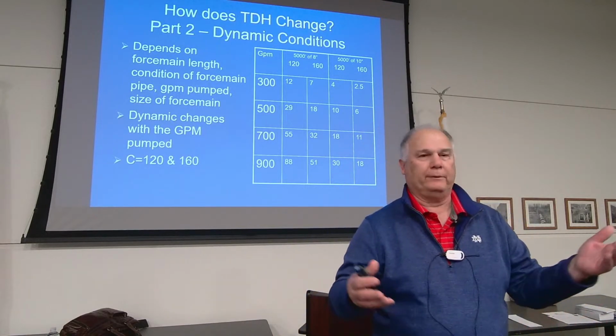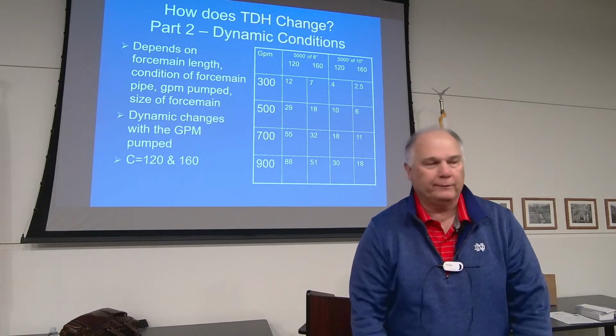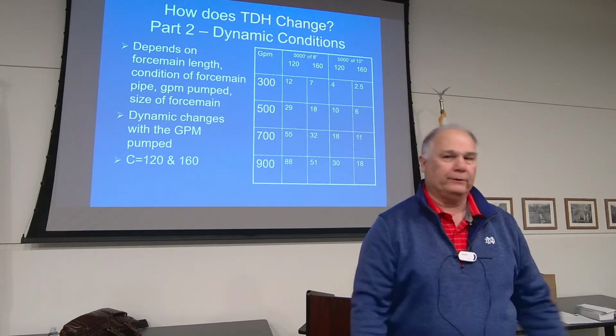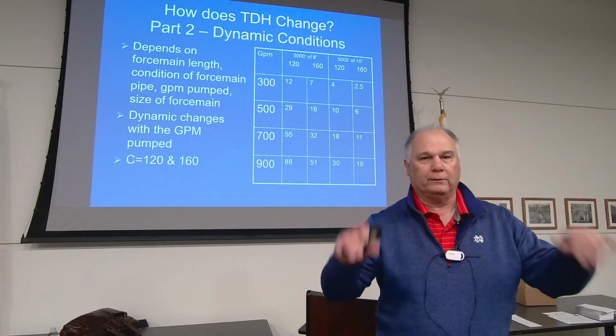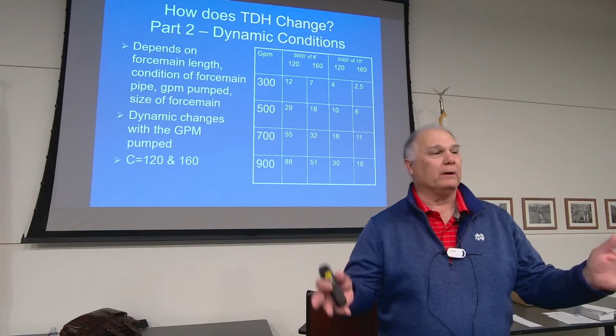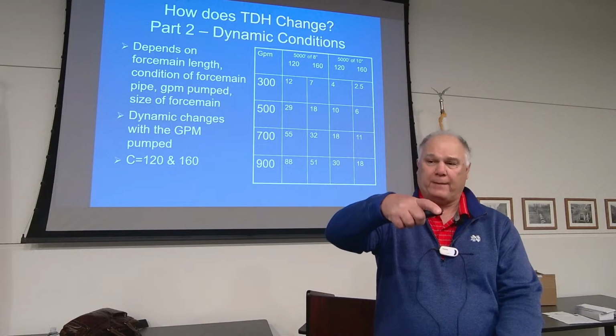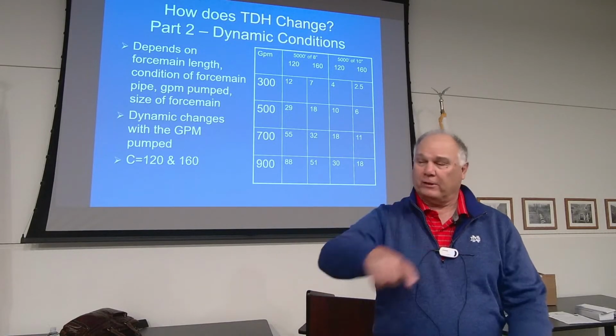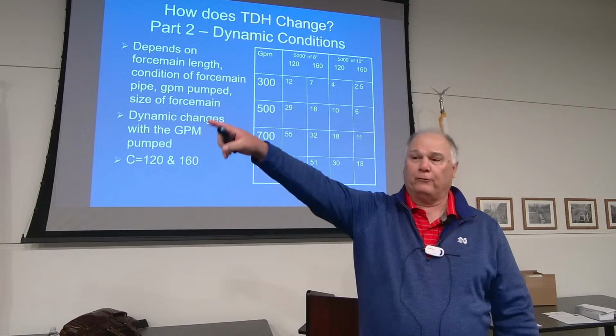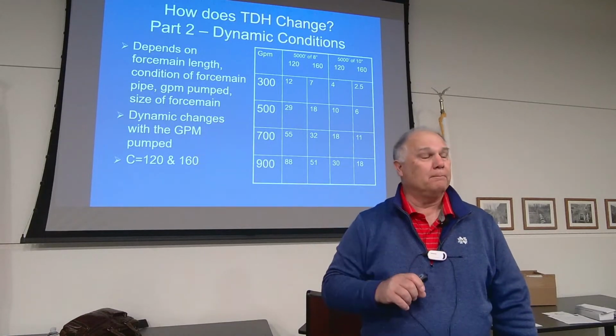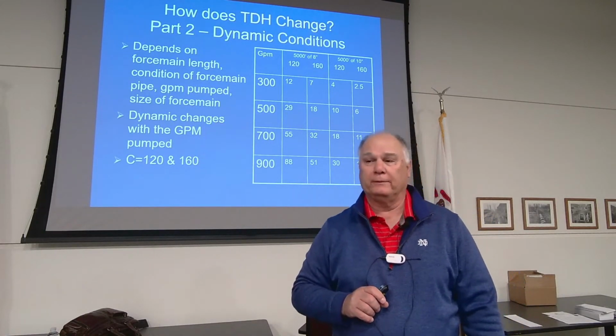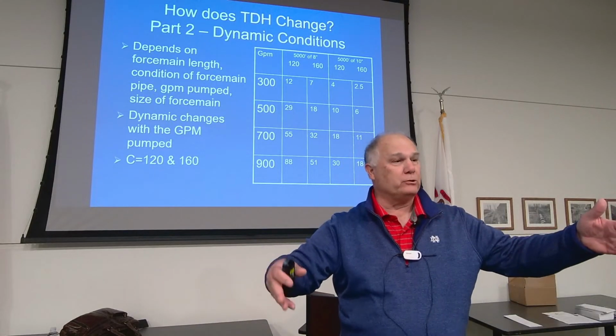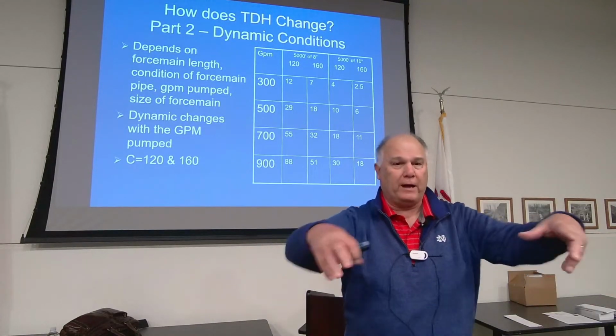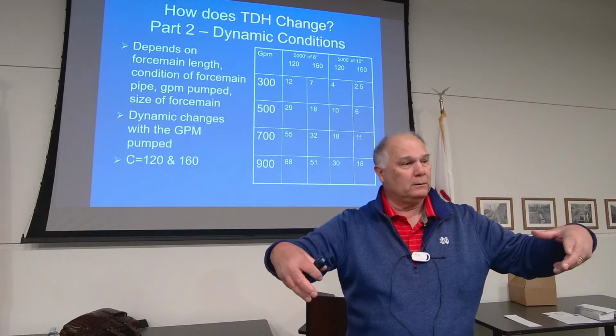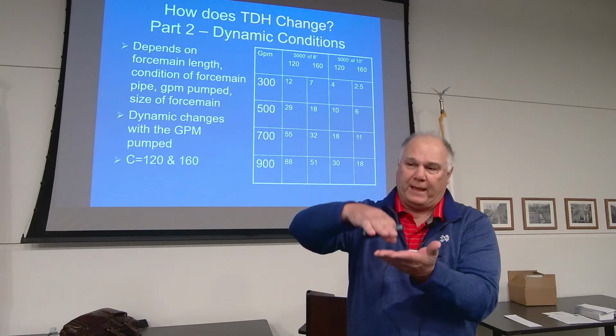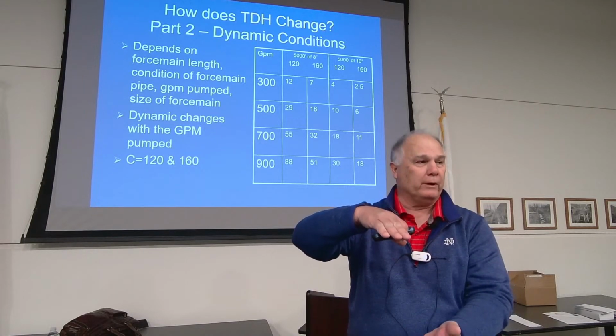So they say, oh, we're only pumping 10 gallons a minute. It's supposed to be doing 1,000 gallons a minute. Well, what's going on? Your pumps stink. Well, once you figure out that maybe this 30-inch diameter gravity sewer we're pumping out for the last half mile is all full of water, we're pumping that out too, maybe that has some bearing on what we're doing. So when you're doing a pump down test, make sure you have a known volume in that wet well so that you're pumping that volume down. It's a true representation of where you're at.